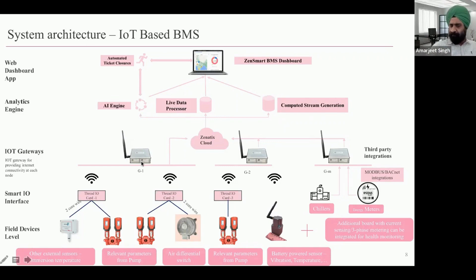At the gateway layer, things are very different. Rather than wiring all IO cards in a large building or across a campus all the way back to a central backhaul controller, you may think of a large building as smaller zones — each zone having its own IO cards, one gateway, and that gateway communicating directly to the cloud. The notion of the building or campus is then a soft notion, formed by aggregating data from multiple zones, each served by its own gateway, coming together as a building or campus entity in the cloud.